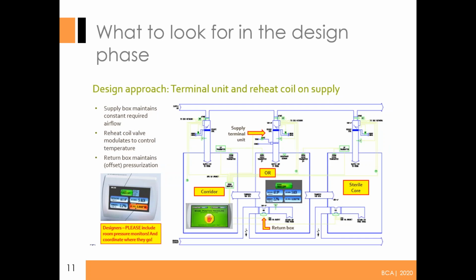And there's a lot of information on here, but mainly I want to go through the points over on the left of the screen. Typically what we see is the supply box maintains the constant required airflow. So for instance, if it's an OR, you want 20 air changes an hour or whatever the setting is. And then second is the reheat coil valve modulates to control temperature. And then the return box maintains offset pressurization. So this is basically you just go from supply to return box.